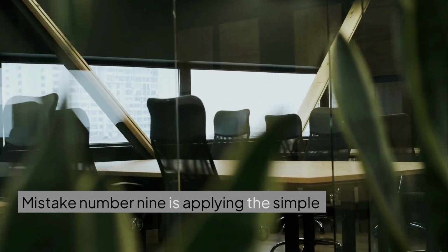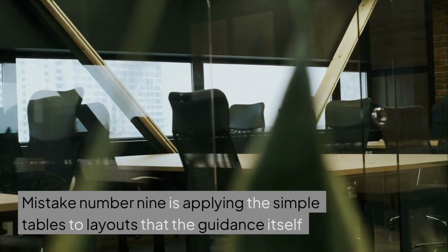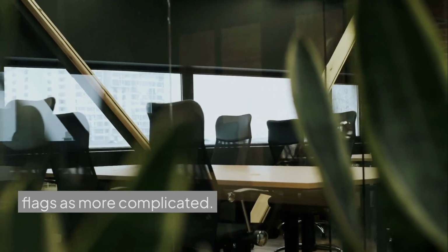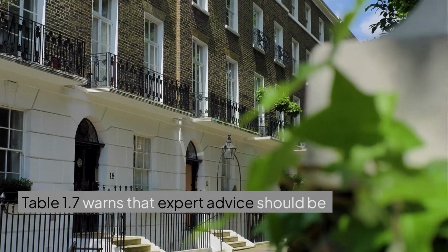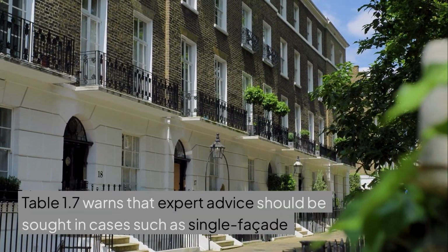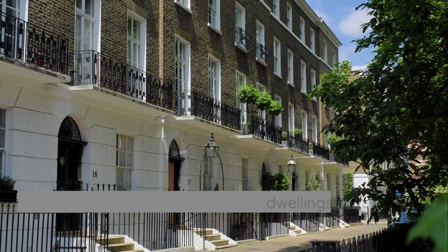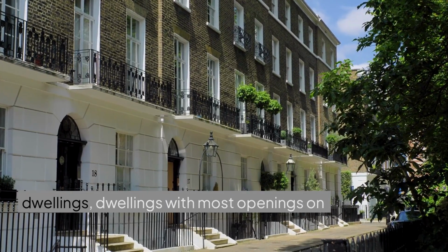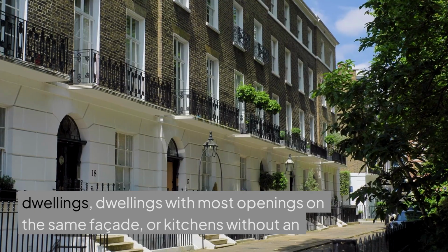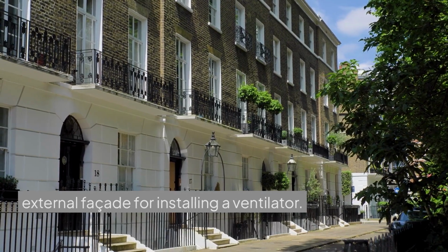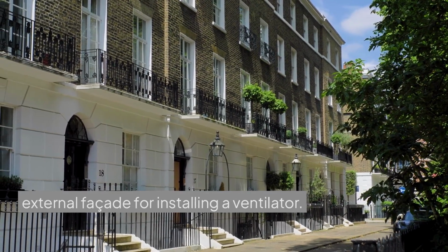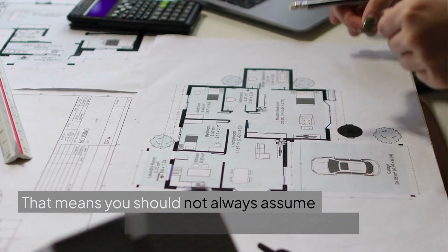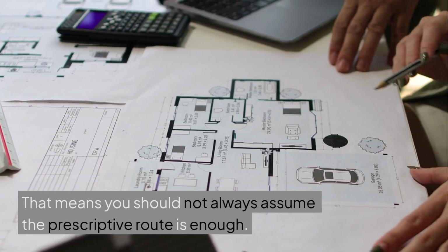Mistake number 9 is applying the simple tables to layouts that the guidance itself flags as more complicated. Table 1.7 warns that expert advice should be sought in cases such as single facade dwellings, dwellings with most openings on the same facade, or kitchens without an external facade for installing a ventilator. That means you should not always assume the prescriptive route is enough.